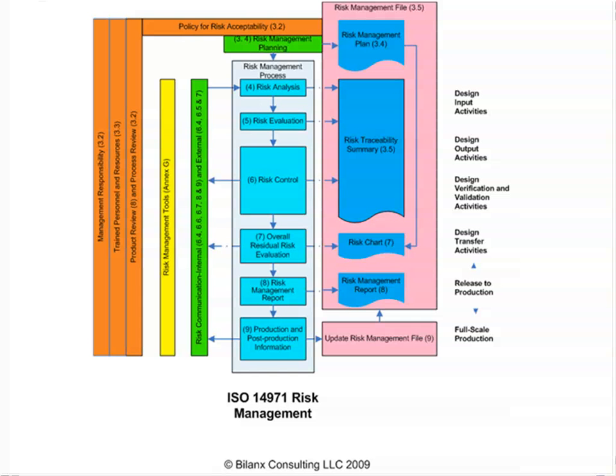The other external communication is communicating the risks for the use of the device to the user so that they are aware of the risk and they know what precautions they should take in the use of the product. Often we communicate those through warnings in the front of our user manuals, but also they're communicated in the instructions for use on the proper use of the product, so that we avoid errors in the use of the product which may expose the user to some risks. Okay, that covers the left side of the diagram.